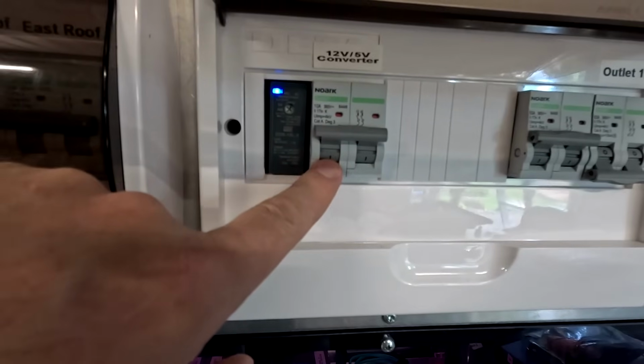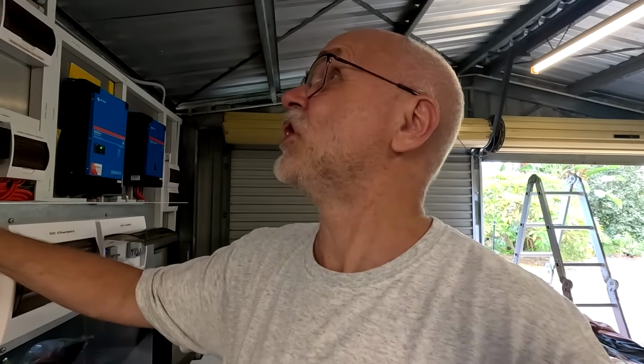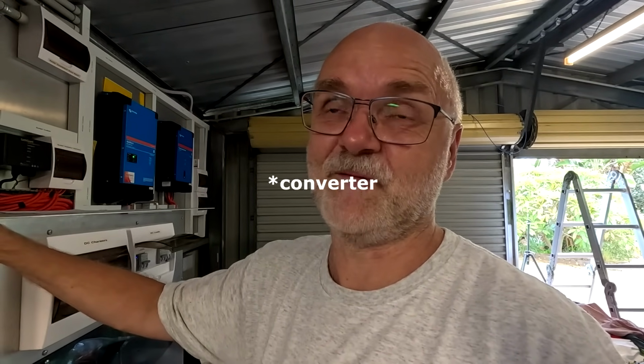We've got a 48 volt breaker and main switch, so to speak, here, on the 48 volt side of this DC to DC converter. If something goes wrong, if there's a short or something, I have to flick the breaker anyway. So at the moment it's directly connected to the output of this converter and going to the fuse block up there in the network cabinet, and then we are fusing our separate loads in this cabinet.